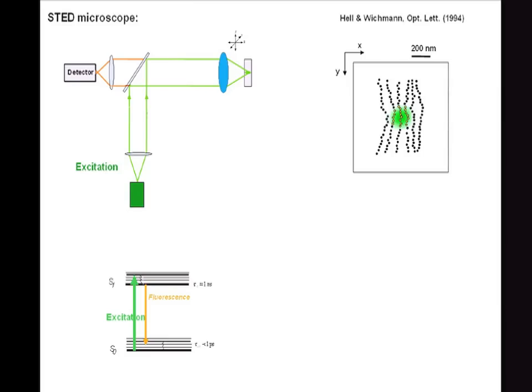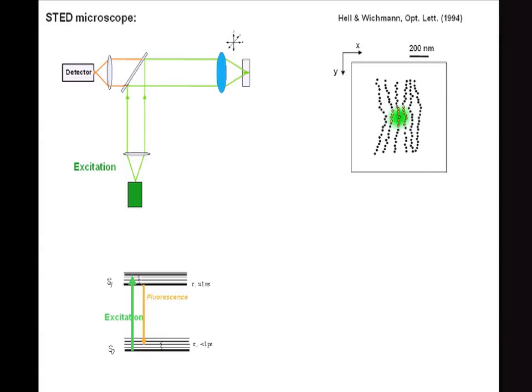You see the focal plane and a sketch of an object — all the molecules that reside within that 200 nanometer diffraction-sized spot will be excited basically at the same time and give off light at the same time. So the detector, which is detecting the fluorescence light, is not able to separate the signal because they will all give off light at the same time. The resolution was simply given by the size of the diffraction spot, and in such an instrument we get an image by scanning this diffraction-limited spot across the specimen — this is typical, for example, for a confocal microscope.